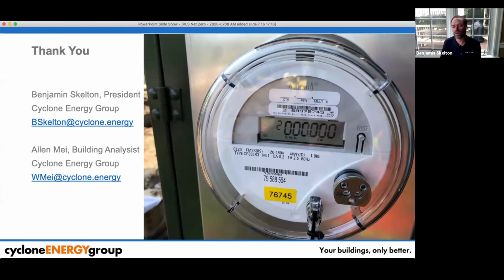Well, in a lot of buildings, the lighting controls are tied to alarm systems or life safety systems. And in this case, it was tied to a security system that was a silent alarm. So when an employee of the company was coming into the building, they were unlocking the building, and they were turning the alarm code off, but they were putting the wrong code in. And it was a silent alarm, so the lights would go to 100% like they would in a security situation, and nobody really noticed in the building. They were open during daylight, and so it was just bright. Nobody really could tell, but the dimming stopped working because the alarm system was overriding it.